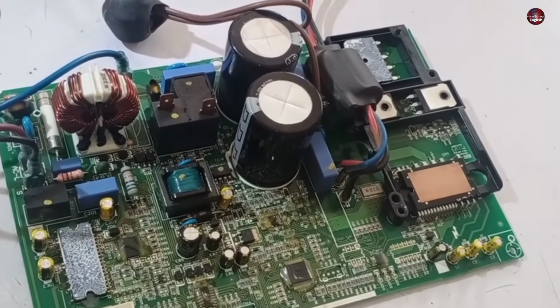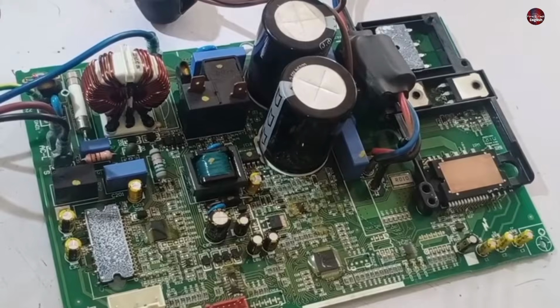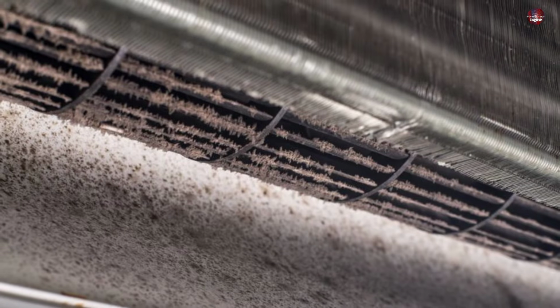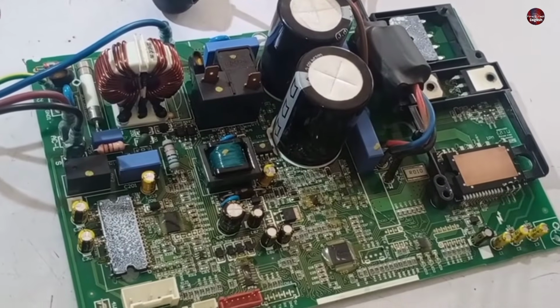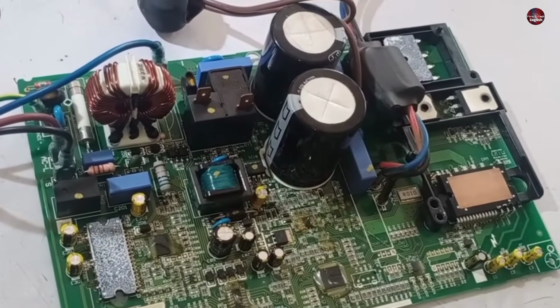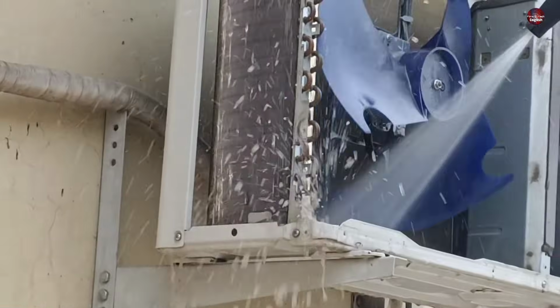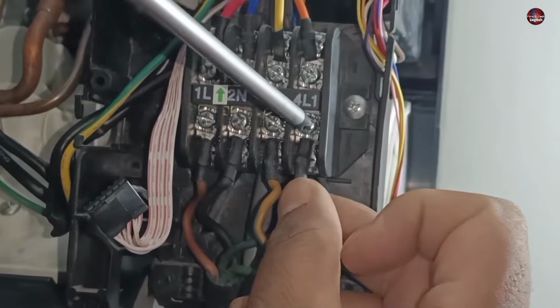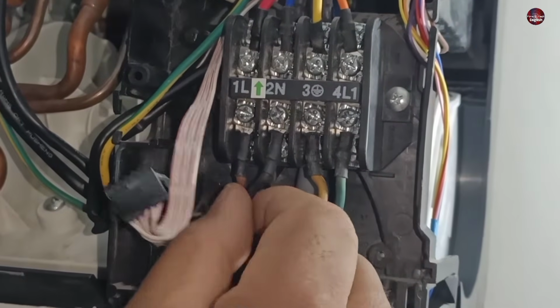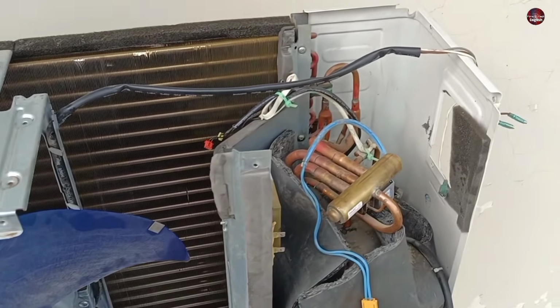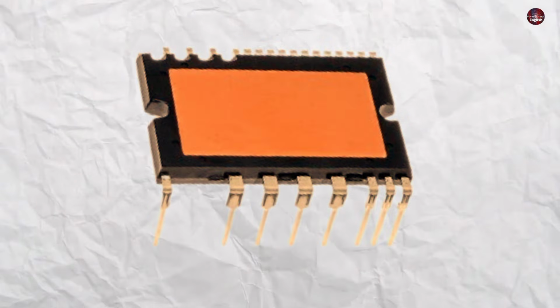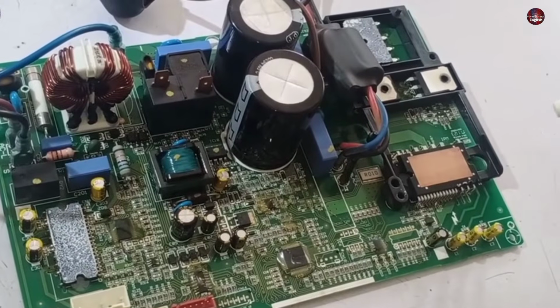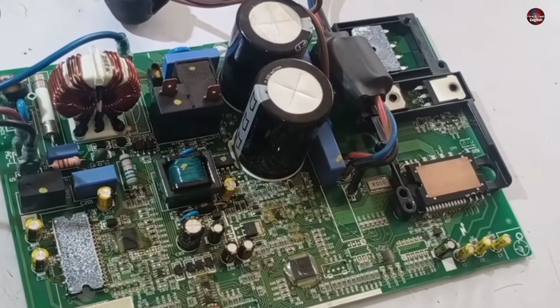I also experienced this in one of the units where I went to fix this error code. The evaporator and the condenser were very dirty and were not cleaned for many years. That air conditioner was showing an F1 error, as actually it is the fault of the IPM. I checked that unit and realized that it was too dirty. So I prioritized cleaning over checking the motherboard. And the rest of the things in the unit like electric connections and the motherboard were fine. I cleaned it. And after cleaning it, the condenser was not heating much, and the temperature of the IPM also went down. I am just sharing what I had experienced when I fixed F1 error codes.